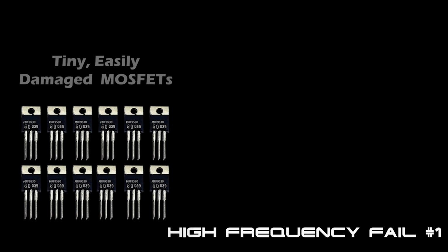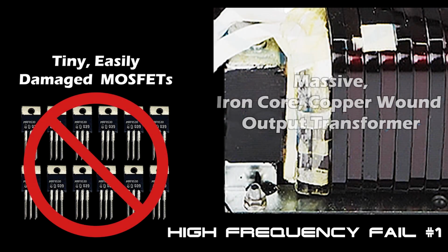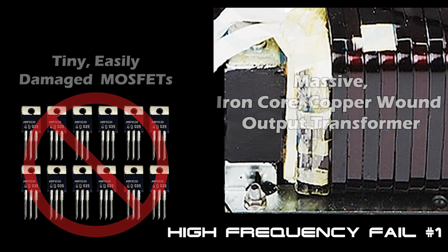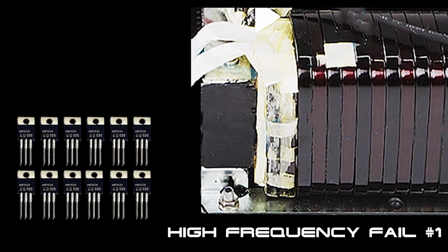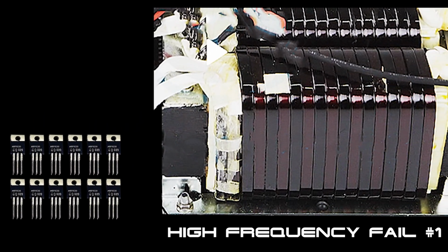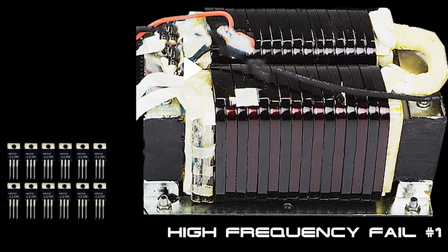In a high-frequency inverter, tiny, easily damaged MOSFETs directly power all of your loads. In a low-frequency inverter, on the other hand, all of your loads are powered by a massive, heavy-duty, iron core, copper-wound output transformer. This massive iron core transformer makes a huge difference in the inverter's life expectancy and surge capacity.